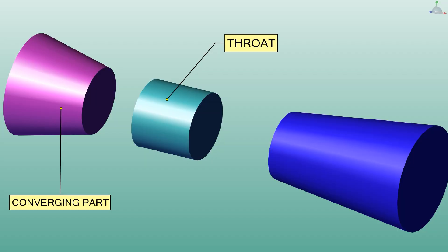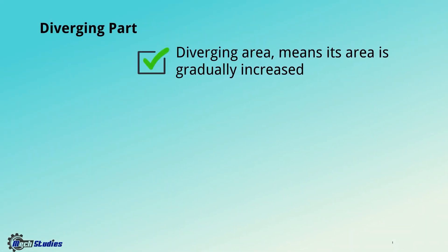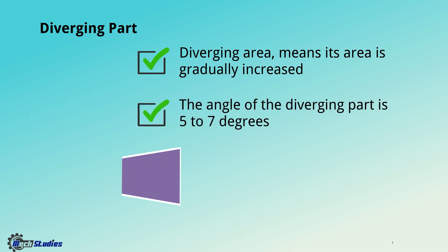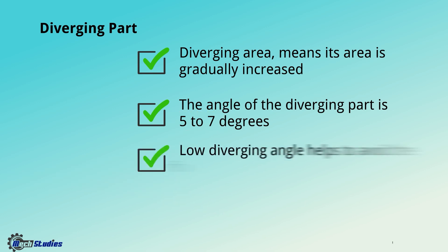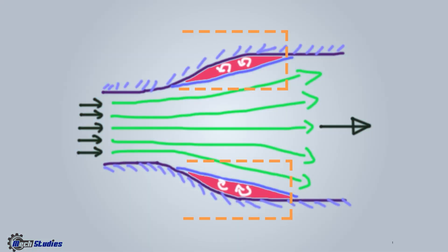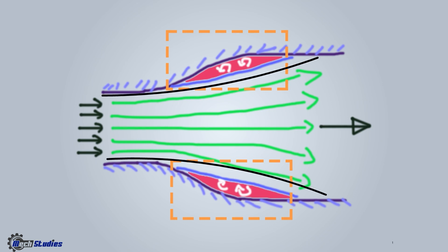Now we will talk about the basic characteristics of the diverging part. The area is gradually increasing. The angle of the diverging part is 5 to 7 degrees. A low diverging angle helps to avoid flow separations and eddy formations. Look at this diagram — this shows eddy formations or flow separations, and a low diverging angle helps to avoid these.